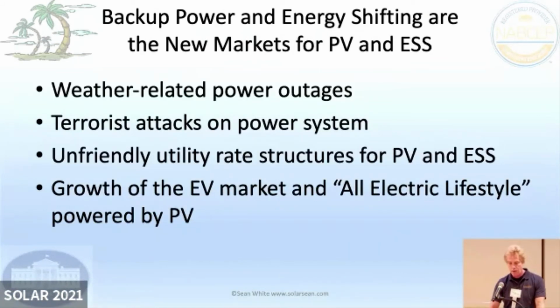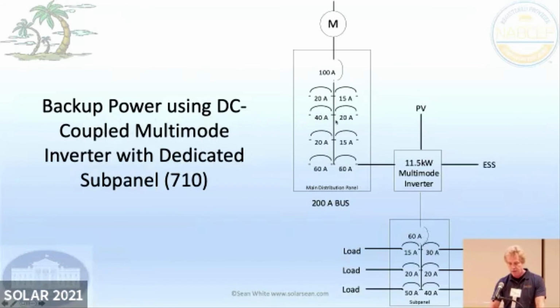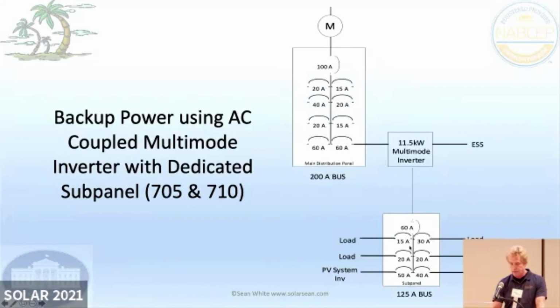So backup power, we're going to have lots of good reasons to have backup power everywhere, everything from preppers to just an all-electric lifestyle. This is one way of doing it that's been around for a while. Multi-mode inverter. So this inverter has an output that's backed up. Let's say we're running on batteries. This multi-mode inverter can back up this sub panel, but this one would anti-island. So this inverter has two modes. It has the ability to do island mode and anti-island mode, disconnect from the grid. So the grid goes down and all these loads still work. So that's just a way that people have been doing it for a long time.